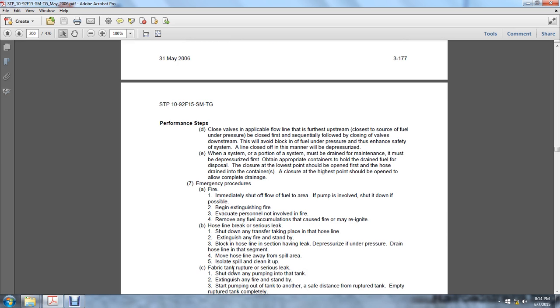D. Close valves in the applicable flow line, starting with the furthest upstream valve, closest to the source of the fuel under pressure. Close that valve first, subsequently followed by the closing of the valves downstream. This will avoid blocking in fuel under pressure and enhances the safety of the system. A line closed off in this manner will be depressurized.